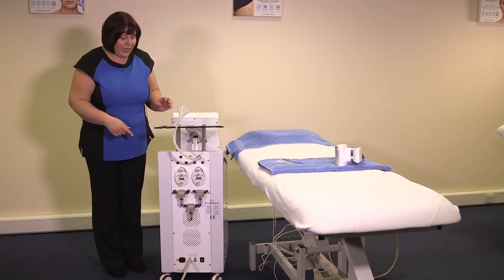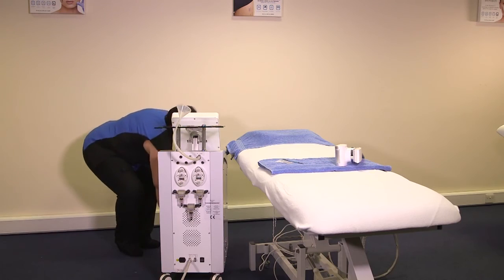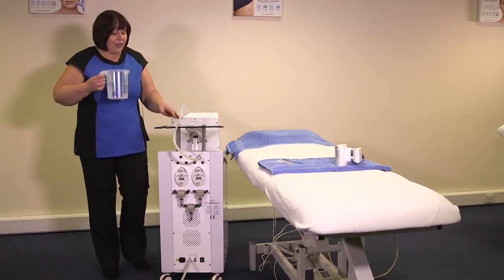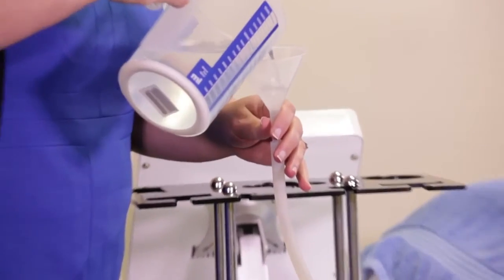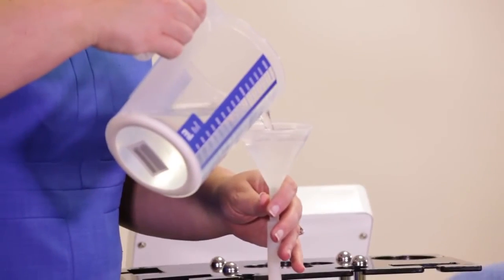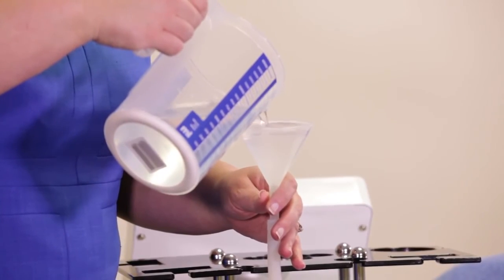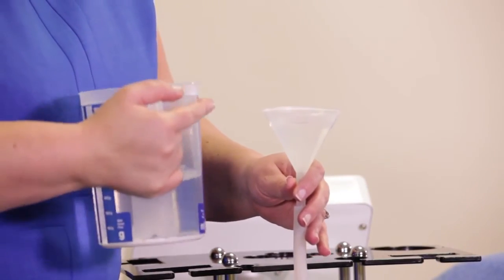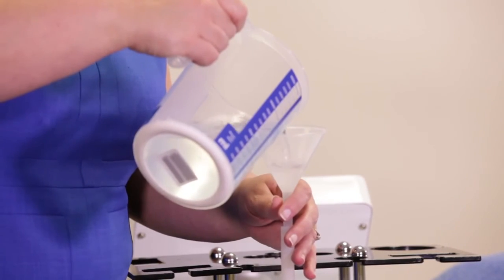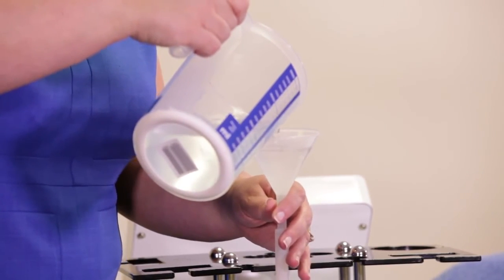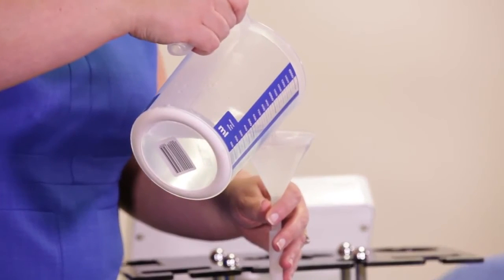So when you have your tubes attached, you need to then take your water. This needs to be deionized water or purified water, and start then to fill your funnel. It's important when you top your machine up that you keep your funnel full with the water. What you mustn't do is fill it, let it drain, fill it, let it drain, because that will put air inside your tank. So you need to make sure your funnel stays full, so we'll push the air away.